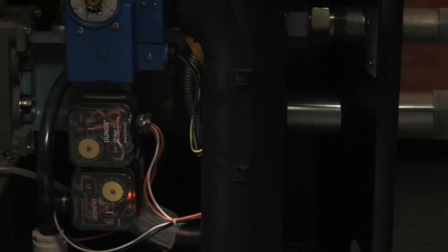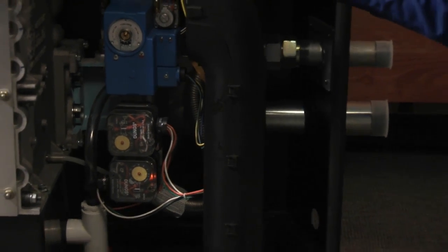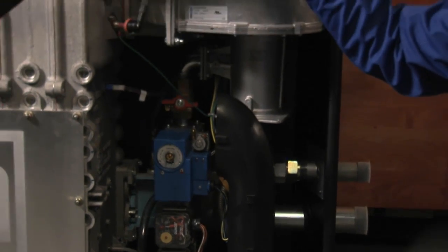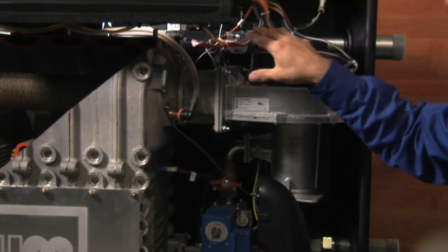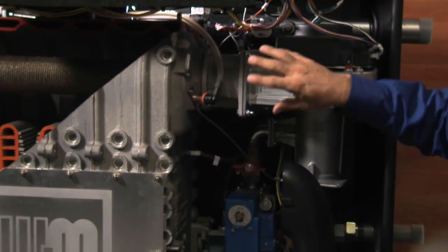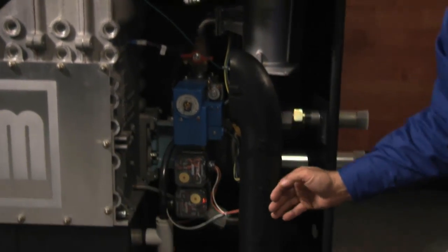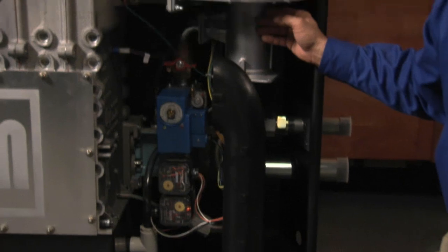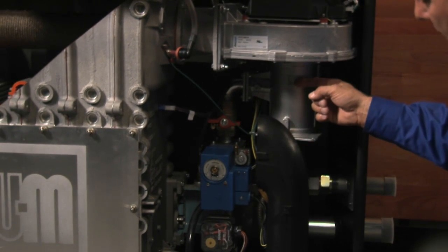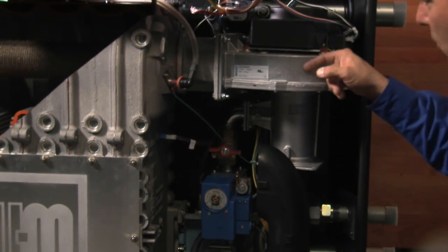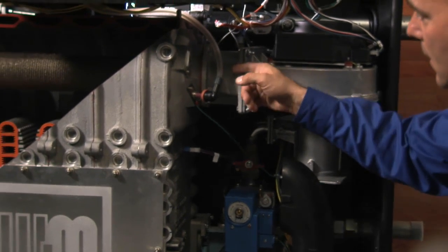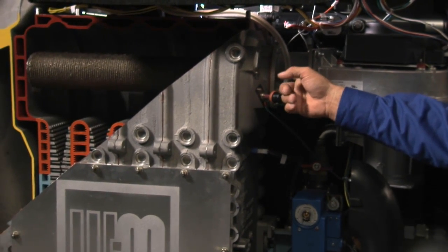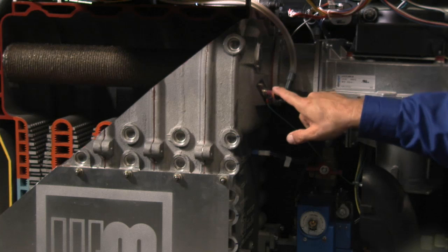This black tube right here, this is an air snorkel. This basically takes the fresh air in that gets dropped into the cabinet area from the fresh air inlet. The fresh air comes into the whole jacketed area, gets drawn in through the snorkel, up into the venturi. The gas and the air mix here. They get swirled together inside the combustion blower. They get injected into the center portion of the burner, and they ignite right here.